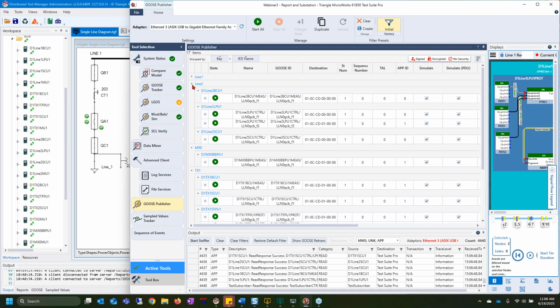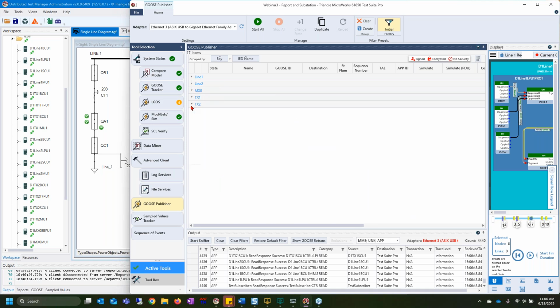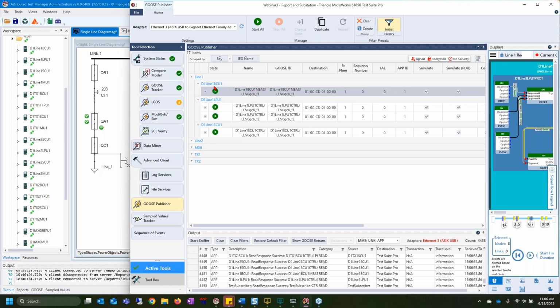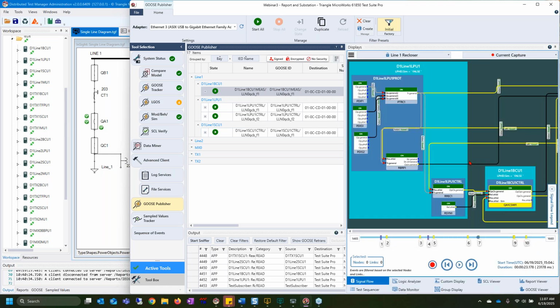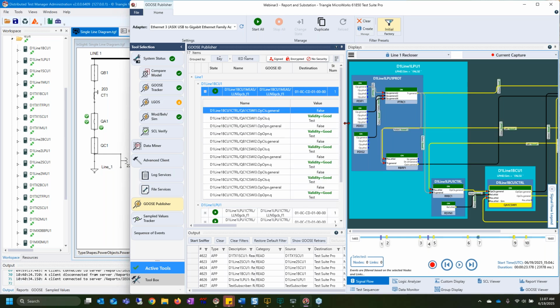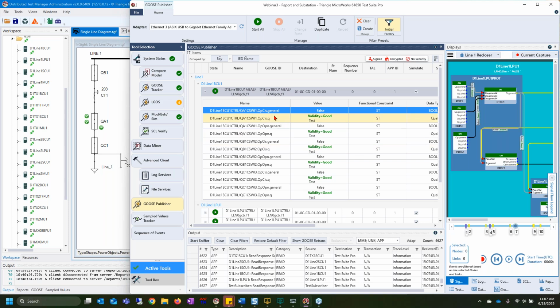So all of my line 1 streams are in here, and we've got our transformer lines. So you can go in and see, just like this BCU was publishing the op open and op close, you can go into that as a simulated stream here and see we've got our op close and op open, and you can issue a publish of GOOSE by clicking the start button without necessarily needing your server to be there. So those are some of the tools within our Test Suite Pro to monitor GOOSE traffic and even generate traffic. And at that, I will hand it back over to Jackson to talk about sampled values.